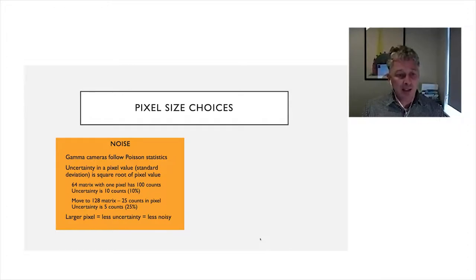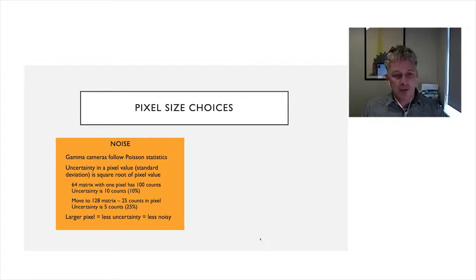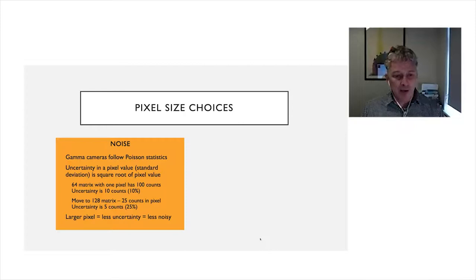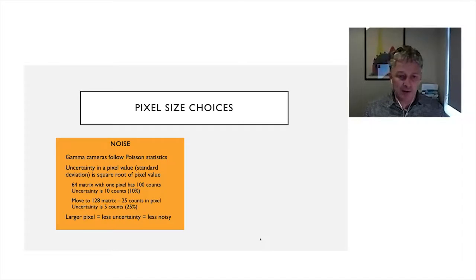If we acquired the same total counts but moved to a 128 matrix, the count density per pixel is reduced to 25 counts per pixel, and uncertainty increases to 25%. Using a larger pixel gives less uncertainty or less variability in the signal and less noisy data. So for certain tests, we might choose a less noisy image by using larger pixels. The compromise of course is spatial sampling — for things like spatial resolution, we need a smaller pixel size.